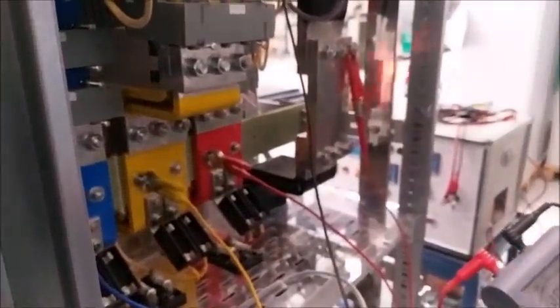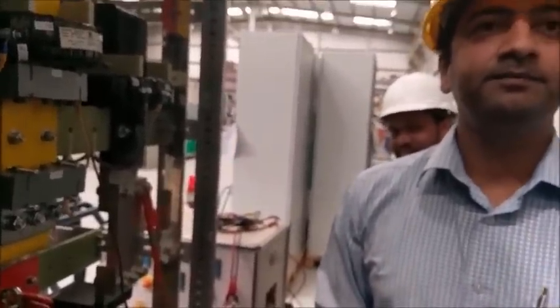Once I push test off, it will come to 0. Now as per standard, as per IEC, it should be more than 100 megaohm. Now it's more than 1000, so it passes. It's very high, good. Like that.